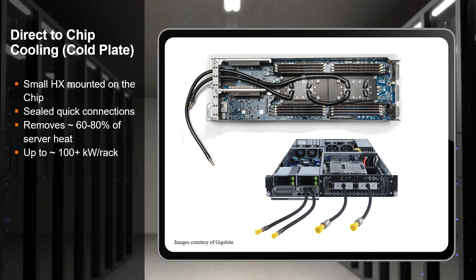What does this look like from a design standpoint? Well, this is like a rack with 4 servers in it. In general, the fluid's coming from a CDU of some kind, and it's usually coming through like a braided hose or a flexible tube of some kind, and then we'll go to a manifold, and that manifold will have additional tubes that go to each server, and then it's returned out the other side. So it looks a little bit like a building in that we're serving multiple floors of a building, but really we're talking about relatively low pressure losses in all this piping, and so we can ignore some of the things that happen in building type designs in terms of pressure disproportionate distributions and things like that.